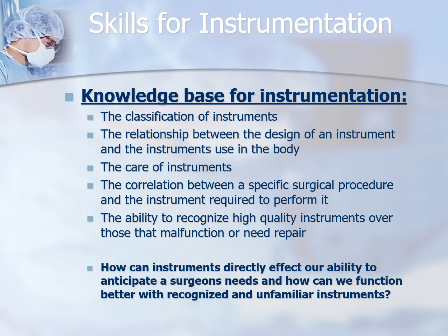When we're setting up our field and we're pulling our instruments to set up our Mayo stand, our job is to look at those instruments and make sure that they're functional. Take the Adson with teeth and squish it together and see if the teeth fit. If it feels weird or something's not right with it, or you're closing a ratchet and it's springing back open, you don't want to give those things to your surgeon.